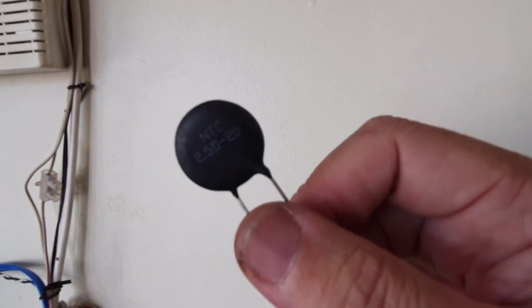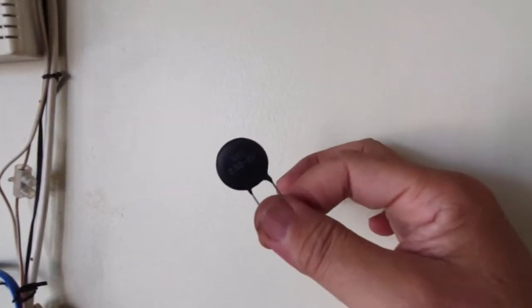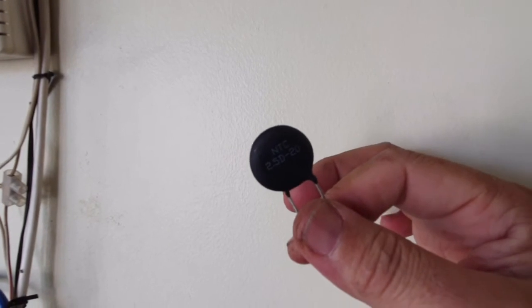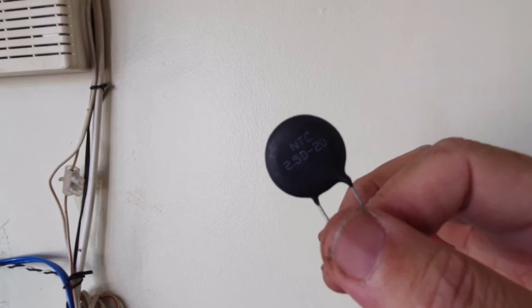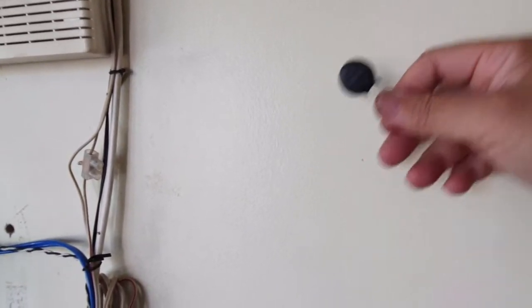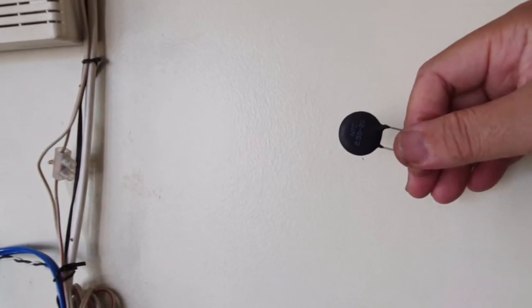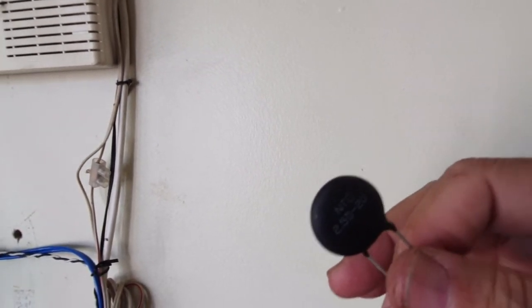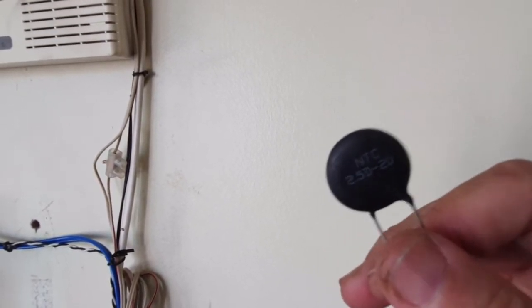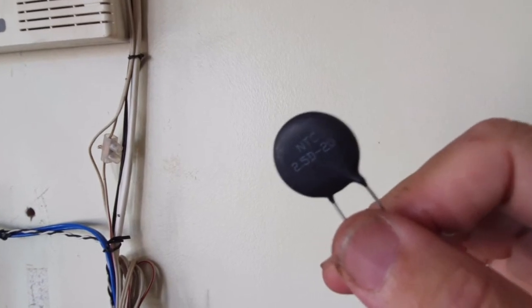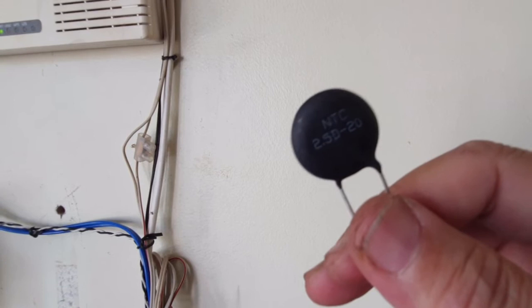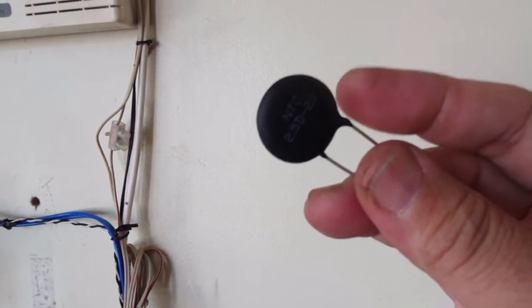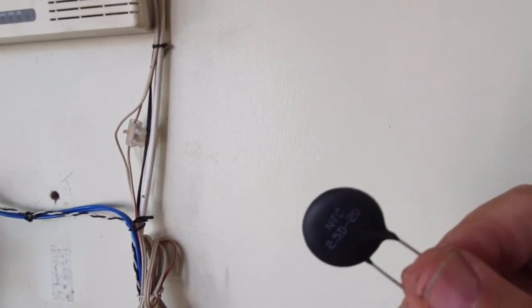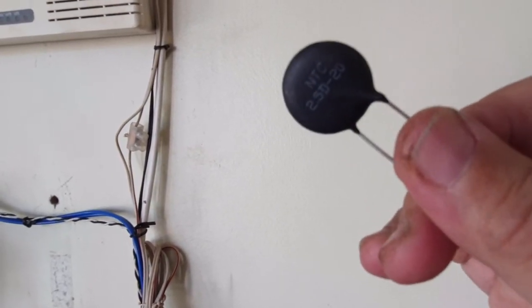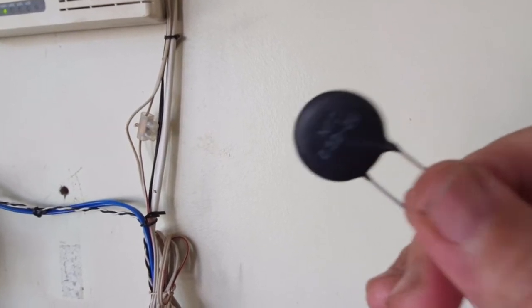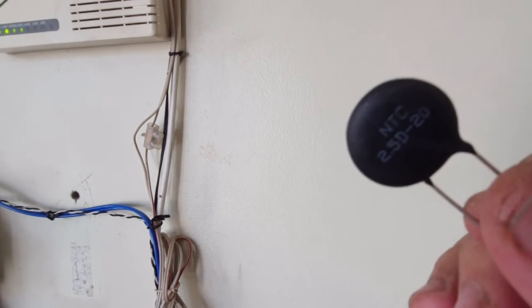Later I'll open up my AC compressors to let you see how I connect them. This is to limit the startup current drawn by the compressor. So the start current is lower, and you have a much smoother startup for the AC. It's useful where you are using off-grid or your AC is on a trailer and you don't have so much power. You need to lower the surge current, because it may be three to seven times the run current. You have to search for the model that's suitable for you. This one works for 220 volts, depending on the area and the amount of current you need. This model will pass about 12 amps. Of course, you can double it in parallel, but it's not recommended.